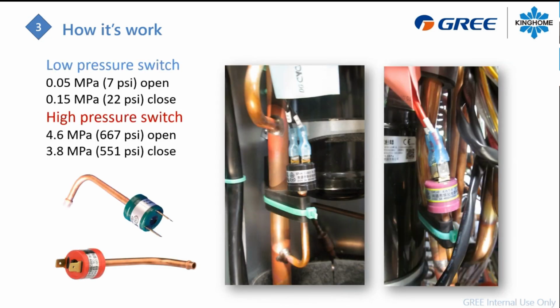You can also find some pressure switches. So you will have a high pressure and a low pressure switch. In the case that those open, you will have an error code related to it. But just be aware that the low pressure switch will open if it's less than 7 psi in the unit, and it will close automatically over 22. The high pressure switch will open if you are higher than 667 psi, and it will close automatically when the pressure goes down to 551.